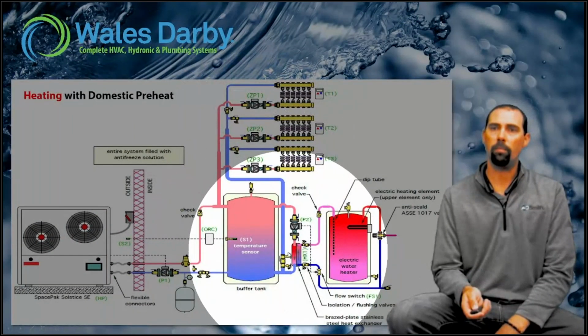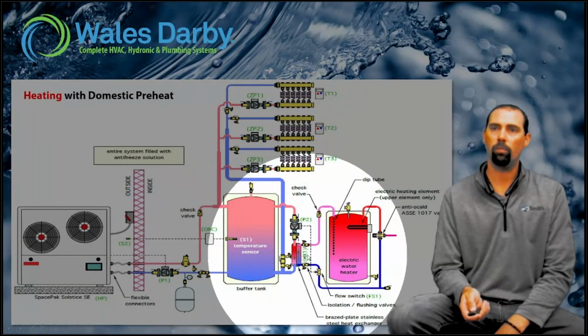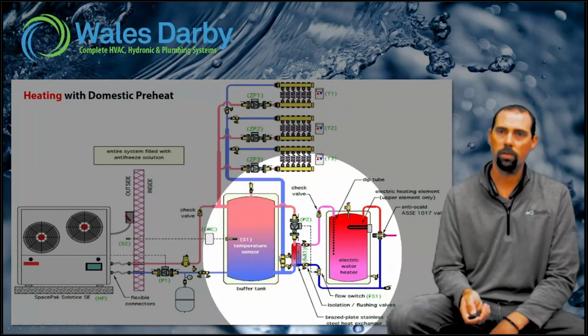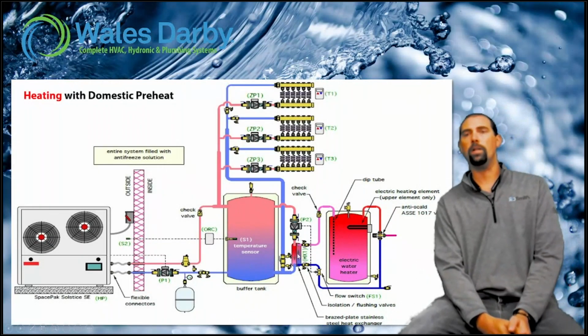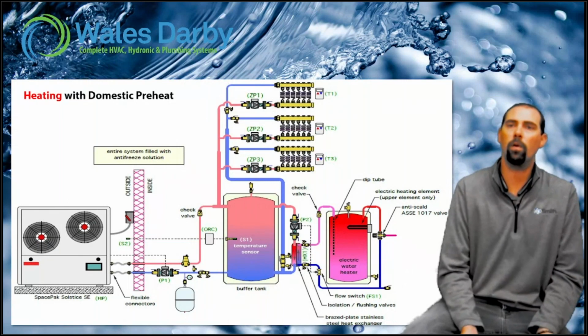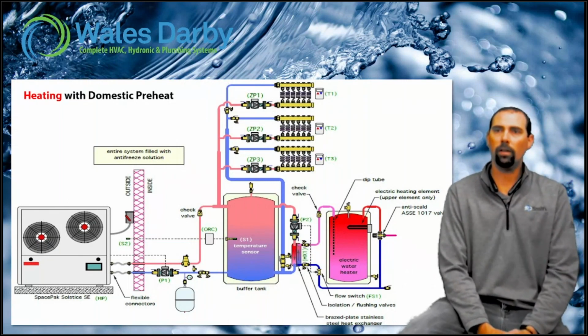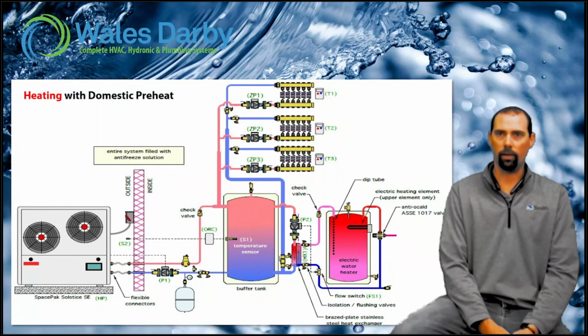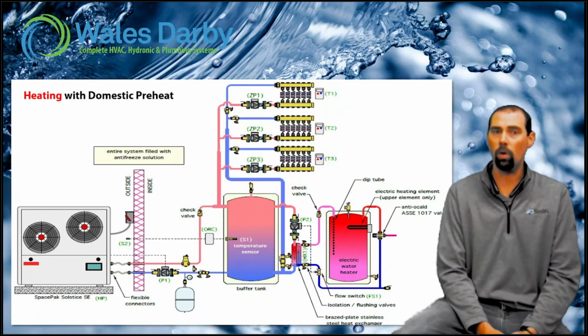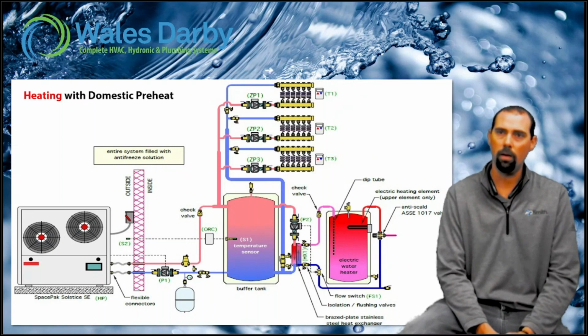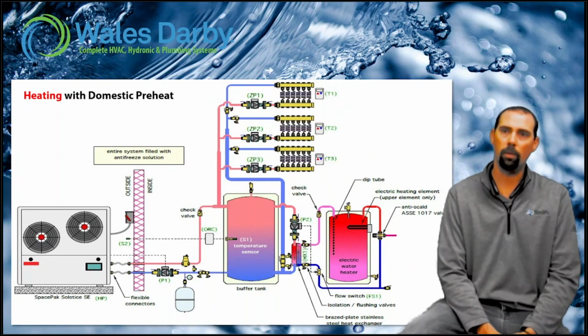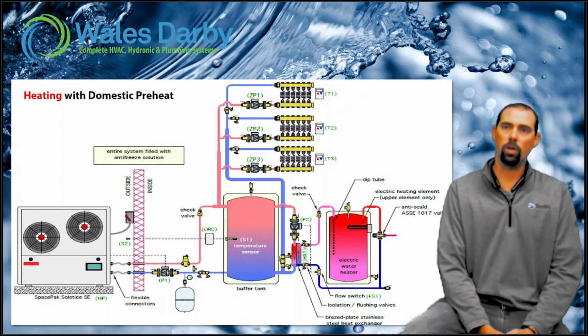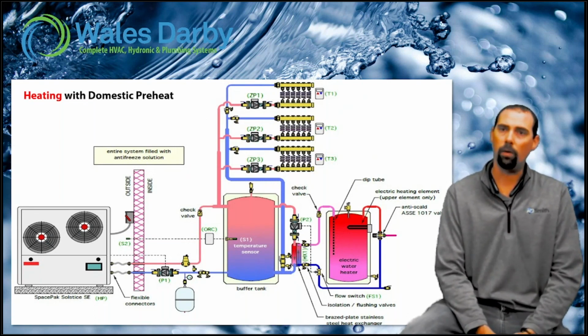We also have a flat plate heat exchanger doing something called preheating for an electric water heater. If I can deliver 110 degrees to that water heater and I have a 130 degree set point, that element in the tank isn't doing much work. So the efficiency of that electric water heater is going to be a lot higher than it would have been without the heat pump there. If we had to heat that tank up constantly with the element, we might not have the storage capabilities of that tank that we do now.